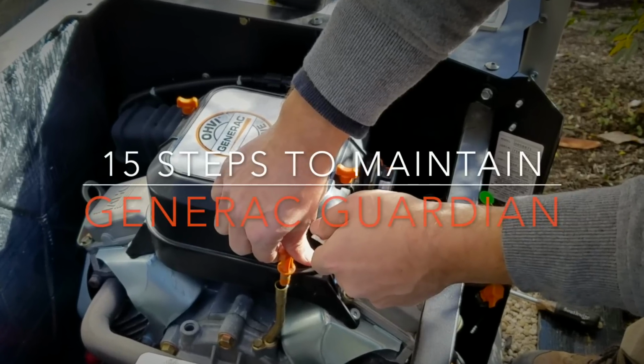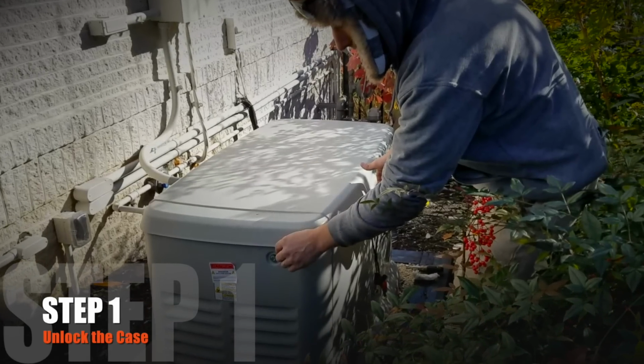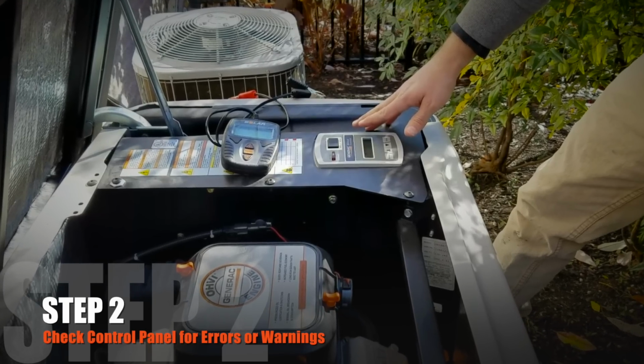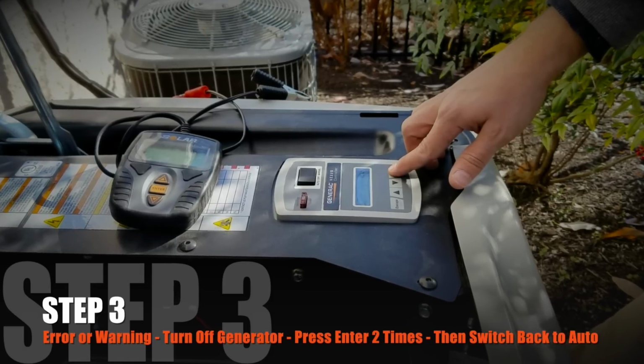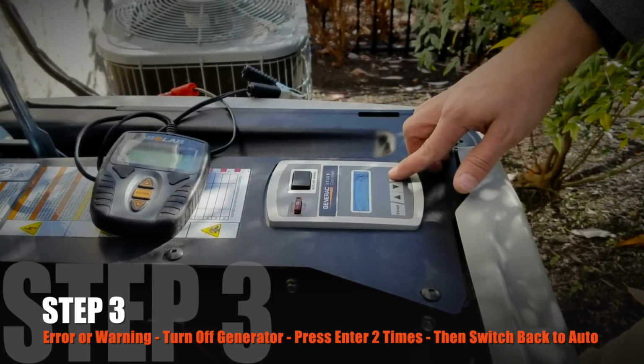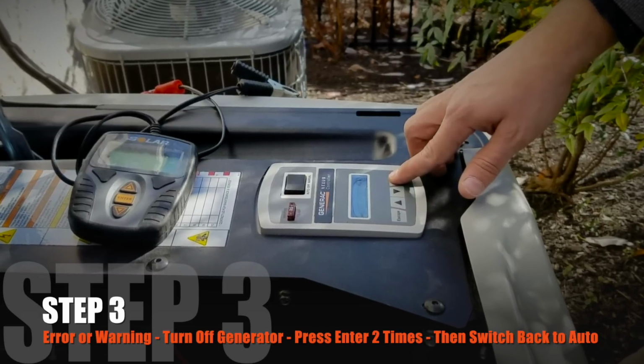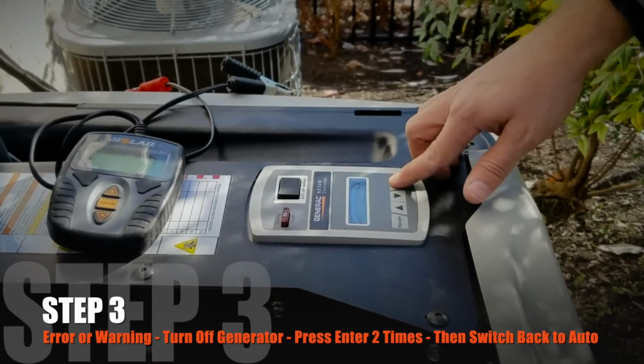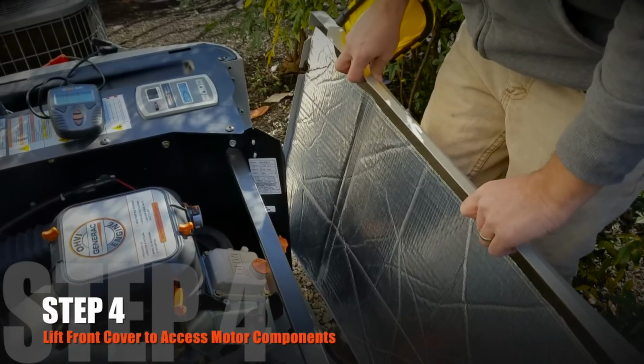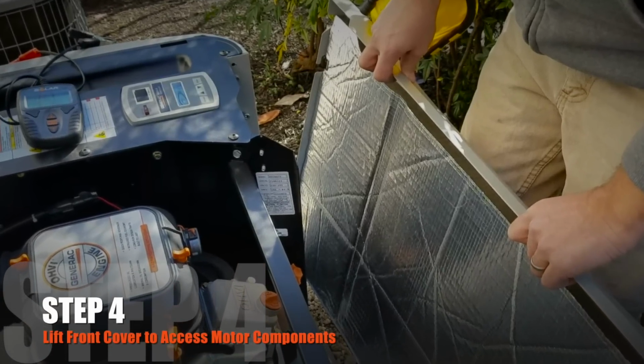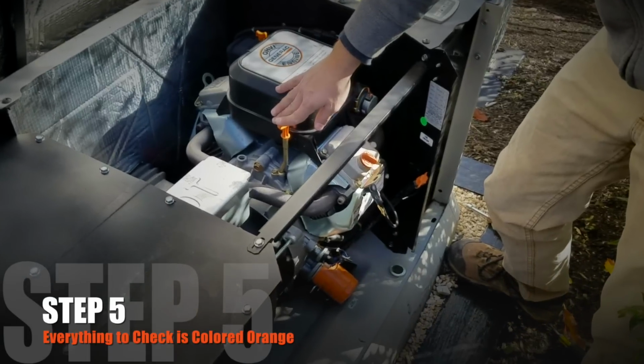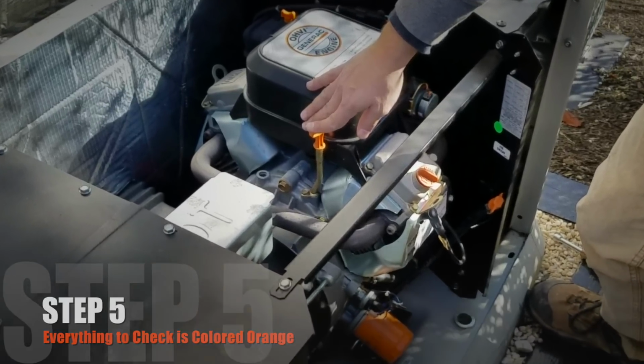Now, let's take a minute and review the 15 steps to complete the maintenance of your Generac Guardian generator. Step 1. Unlock the case of your Generac generator. Step 2. Check the control panel for error or warning alerts. Step 3. If there are errors or warnings, turn off the generator to clear them, then push the Enter button 2 times. Push the Auto button to see if the error message returns. Step 4. Lift the front cover to access the motor components. Step 5. Everything you need to check will be colored orange.